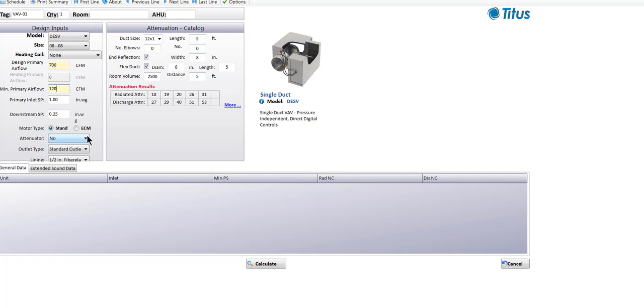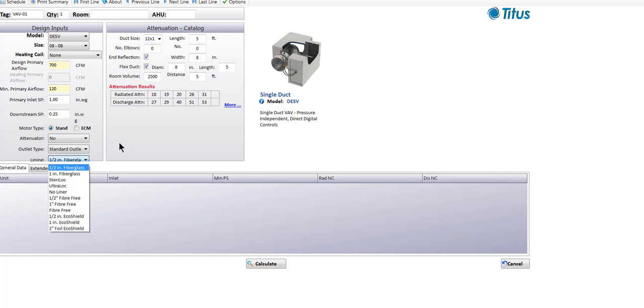There are some other options down here. One would be attenuator — it asks yes or no. An attenuator in our terminology usually refers to an integral attenuator, which is just lined ductwork. Selecting yes for attenuator gives you an integral attenuator on the unit, which basically extends the rectangular casing by two feet of length, exposing the airstream to two feet of lined duct.